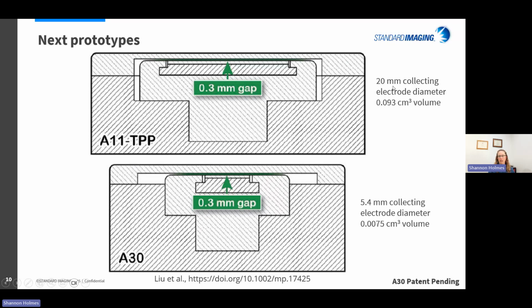That one has the 20 millimeter collecting electrode diameter matching our A11, which gives it a 0.3 millimeter gap. That's a 0.093 cubic centimeter volume. We also made one with a smaller diameter, and that's the one that ultimately got named the A30. It has a 5.4 millimeter collecting electrode diameter, which puts its volume, with that 0.3 millimeter air gap, at 0.0075 cubic centimeters. That's almost exactly in line with our A16 microchamber, the smallest microchamber that we make. So we were relatively confident in making this prototype that we would have enough signal in a conventional cobalt beam to enable calibration of this, so that we can link back to established NIST-traceable calibration methods with this chamber.